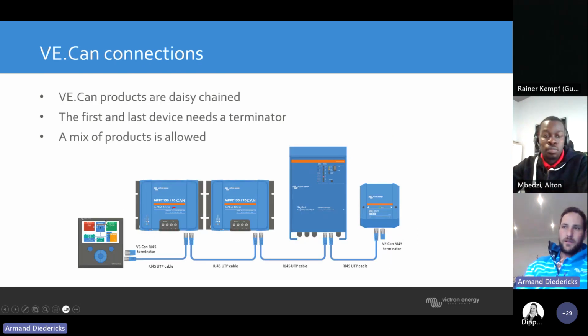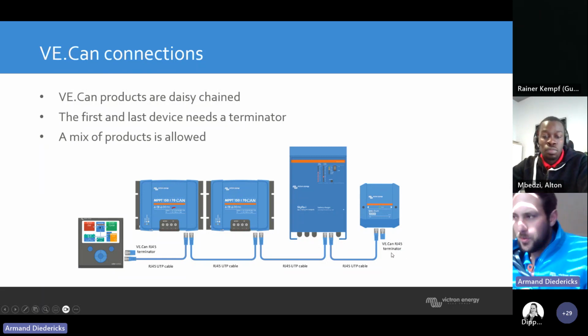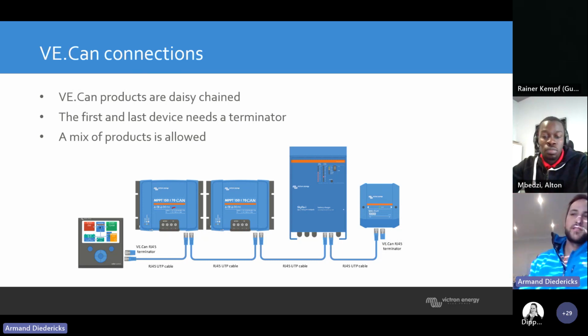VE.CAN connections: VE.CAN products are daisy chained as well, the first and last device needs a terminator, as I mentioned. Same with the VE.Bus - the VE.Bus won't give you issues, but the VE.CAN will definitely give you issues if it's not terminated. So we've got the GX device with the MPPT CAN interface and the Skylla, and the links will be connected to the battery.